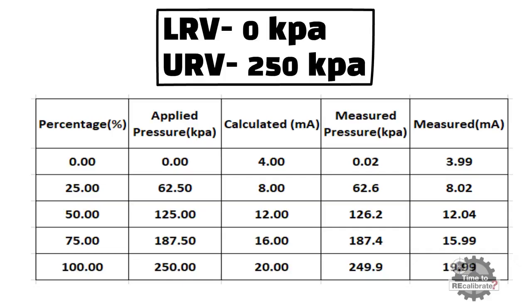Now, apply 62.50 kPa of pressure to transmitter by using pressure calibrator, and transmitter display will show you the measured pressure value. Measured value should be near to 62 kPa. Plus or minus 5 kPa deviation from standard value should be acceptable. Also, note down the measured milliampere value, which is measured by the digital multimeter. Measured milliampere value should be nearer to 8 milliampere.